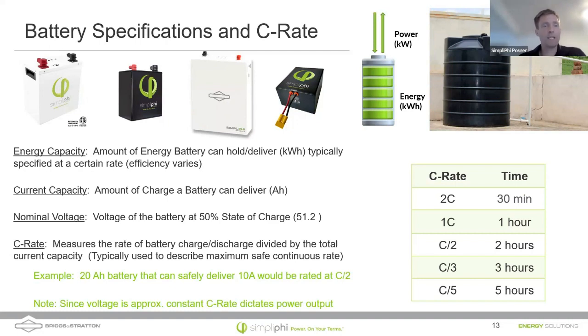The maximum rating for our batteries, which is typically used to describe the maximum safe rate of continuous charge or discharge, is C/2. For most of the prismatic cells, it's typically a little bit less. As an example, a 20 amp hour battery that can safely deliver 10 amps would be rated at C/2, right? So you can take the capacity of the battery in kilowatt hours, divide that by 2, and you'll get the power output of the battery. So a 3.8 kilowatt hour battery for us can discharge at half that, or 1.9 kilowatts, continuously and safely.